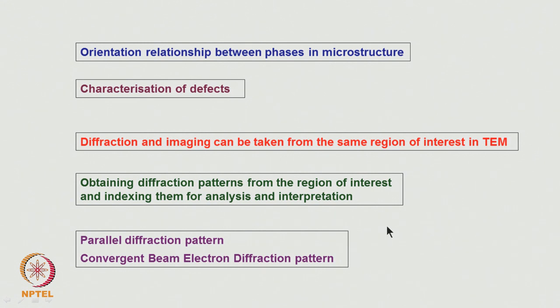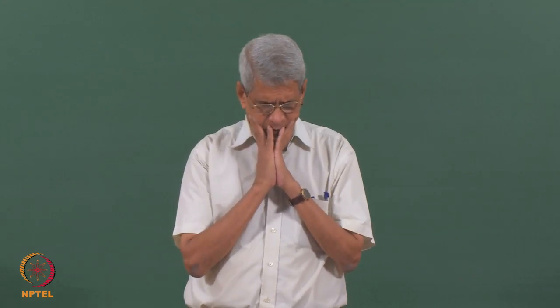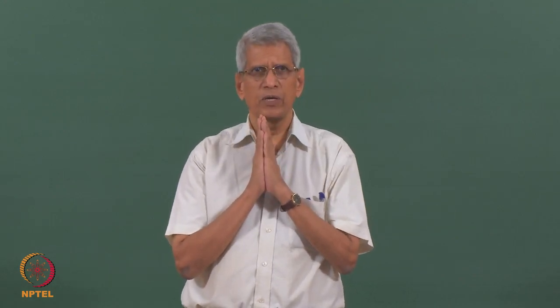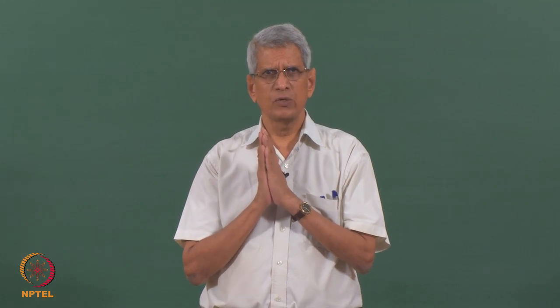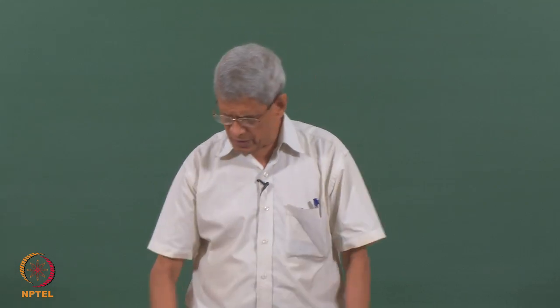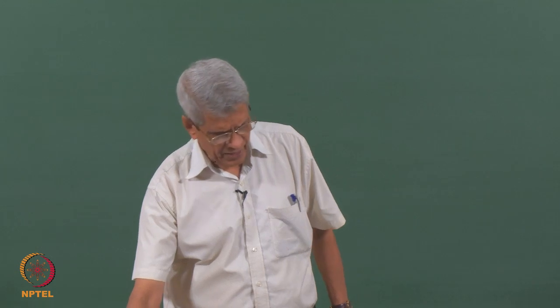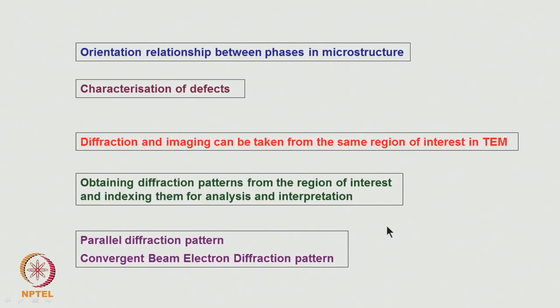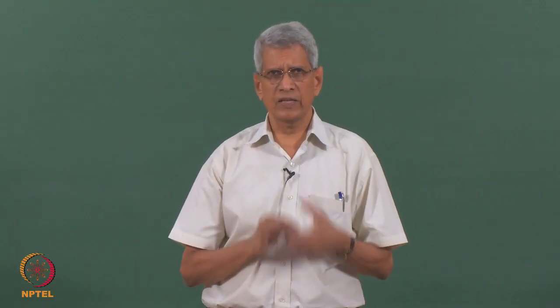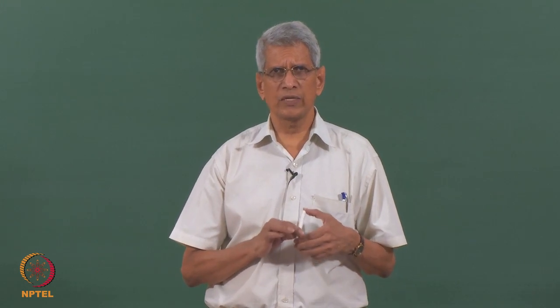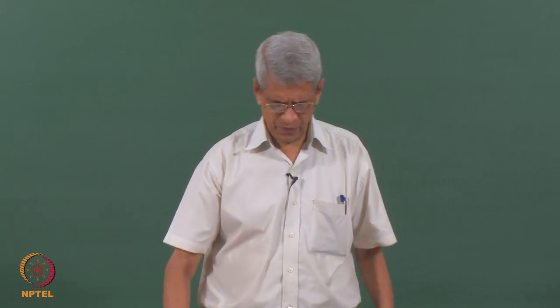We can use the microscope in both imaging and diffraction mode. In diffraction mode, we can use it in parallel diffraction — what we call selected area diffraction mode — and also in convergent beam electron diffraction (CBED). CBED can be used to get information not only about crystal structures and accurate lattice parameters, but also about space group and point group symmetry.